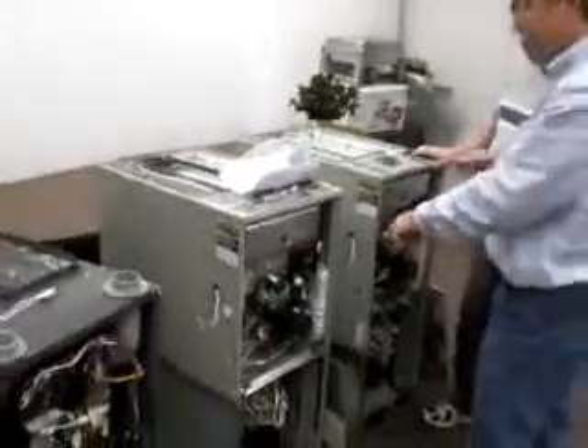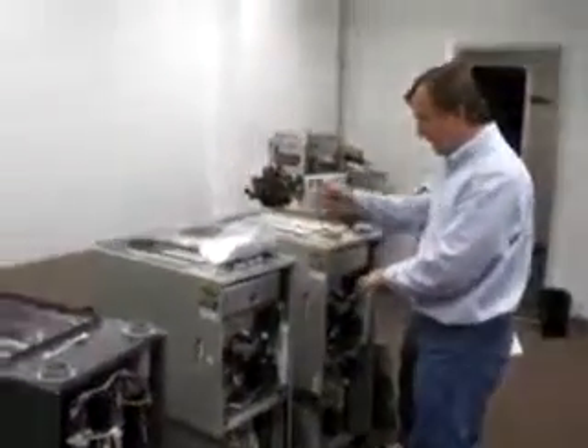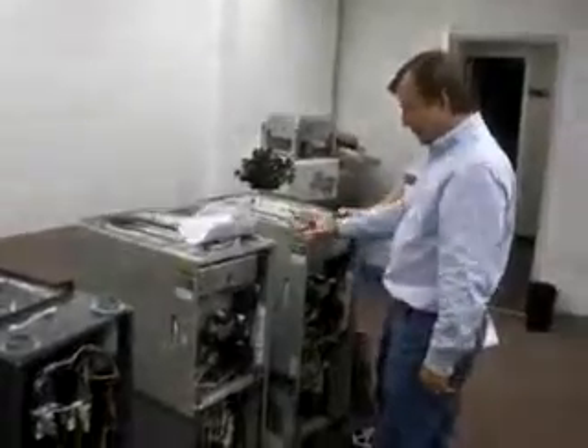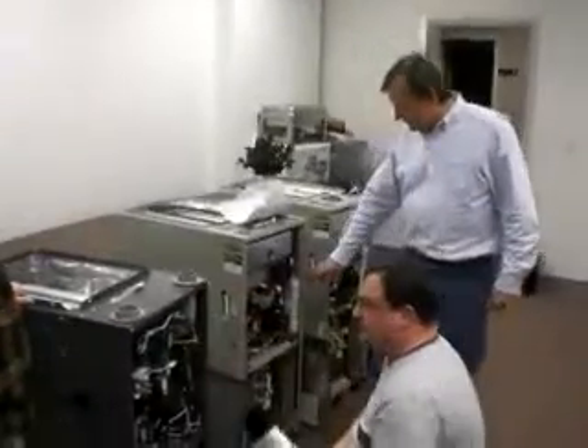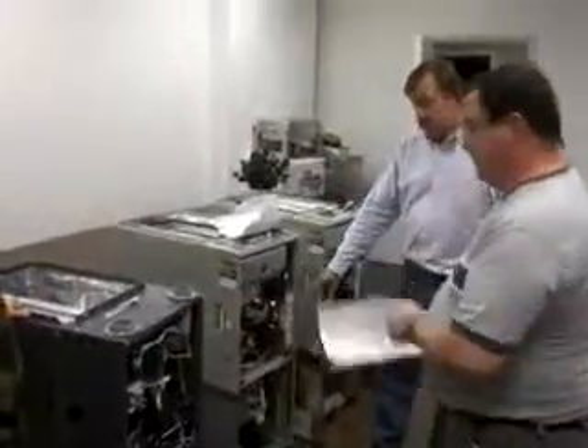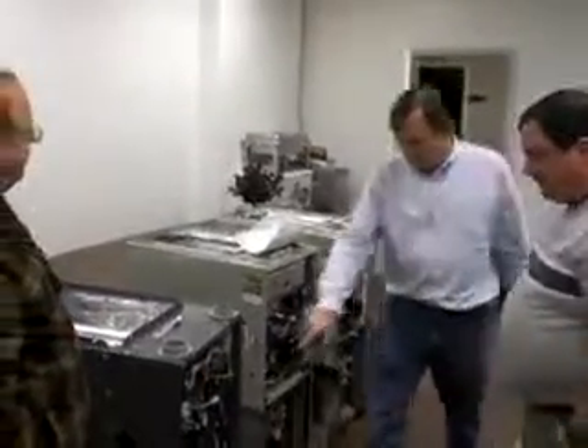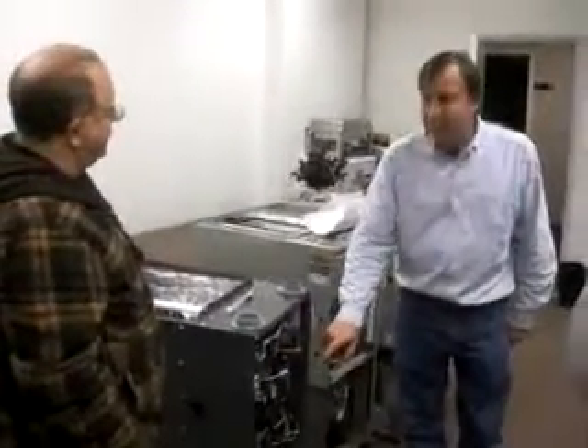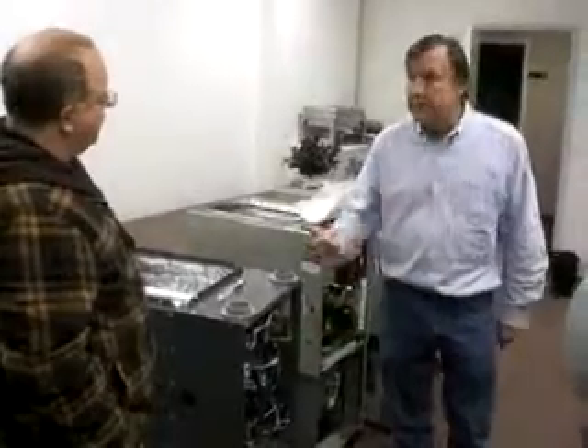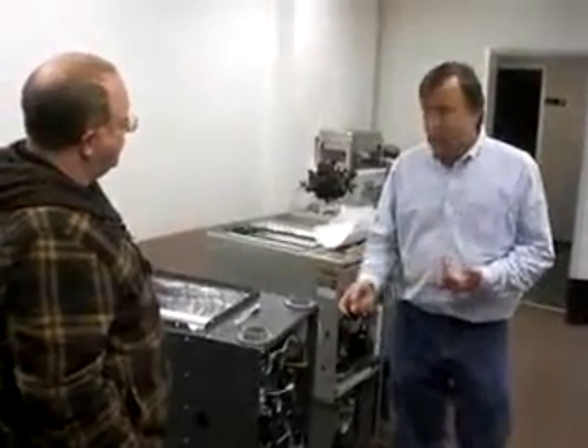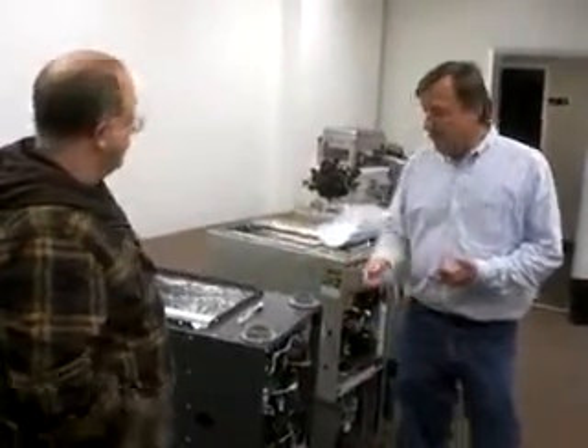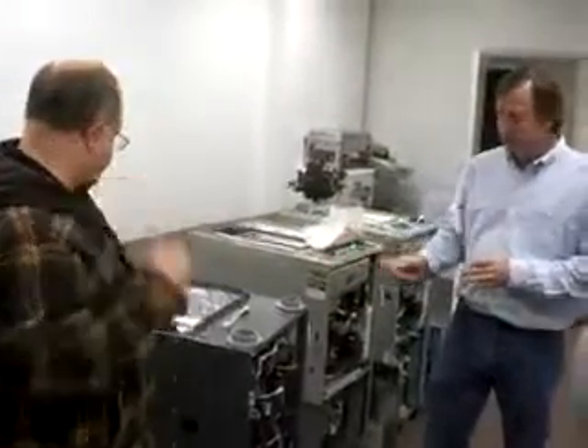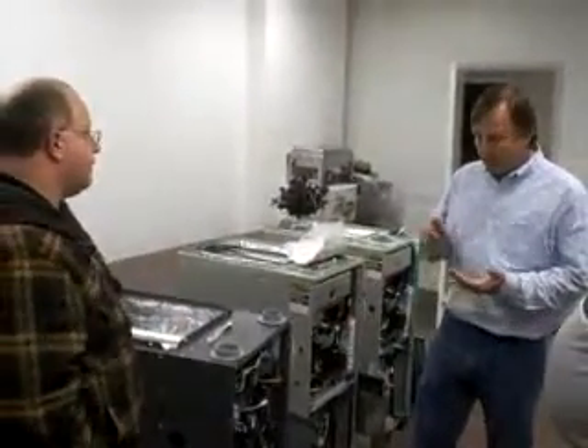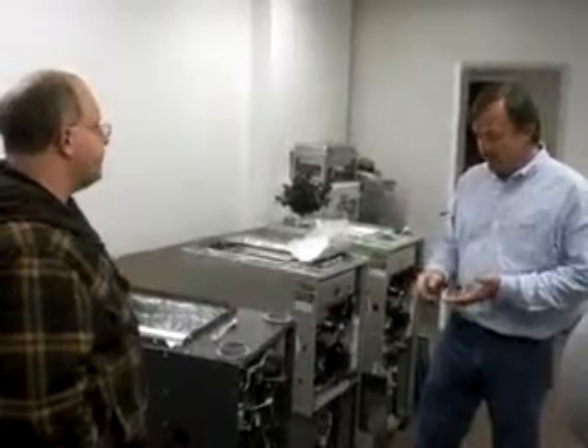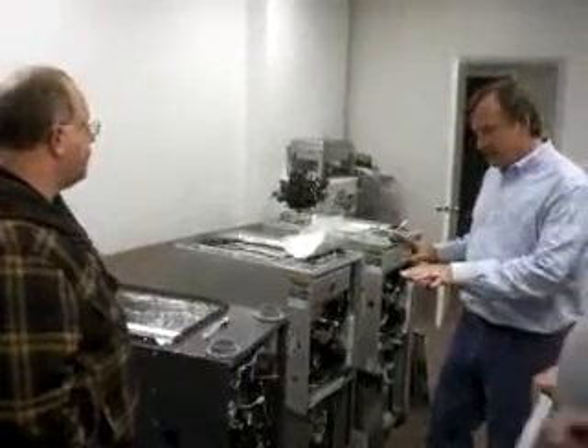Okay, but to further the advantage of having a low energy venter, because we don't need all that velocity, we don't need that volume to go through the system. Our low energy venter is rated at 1.0 amps. The competitor is 2.8 amps, okay, which tells us there's more horsepower required to move the products of combustion through the tight heat exchanger, okay, and there'll be more noise and it uses more energy.